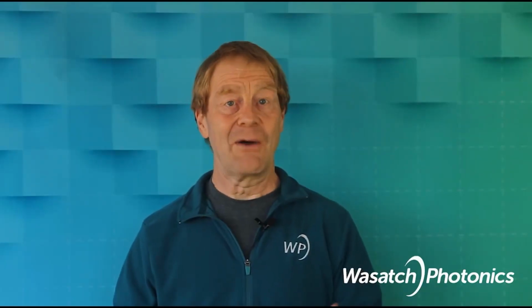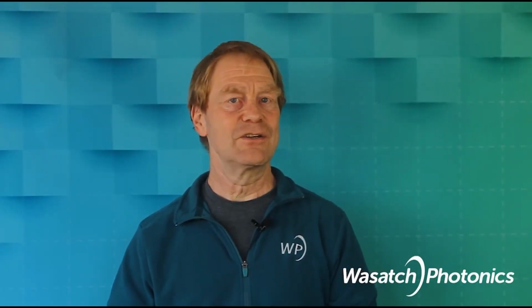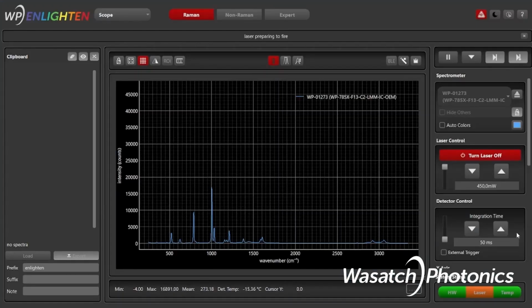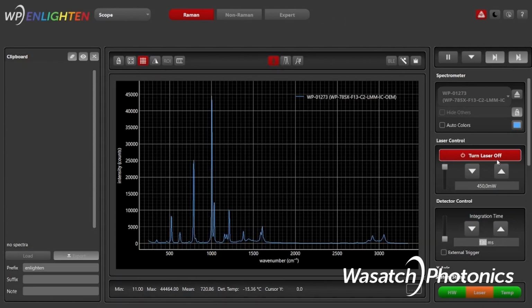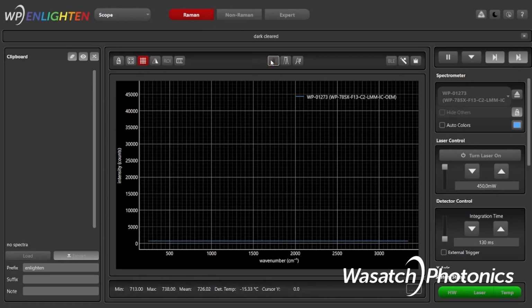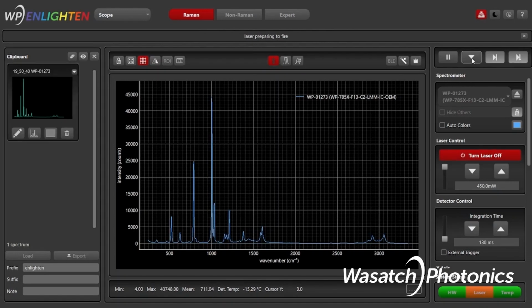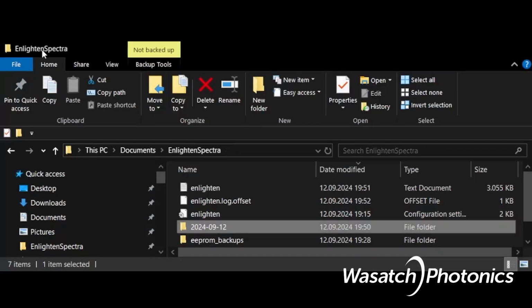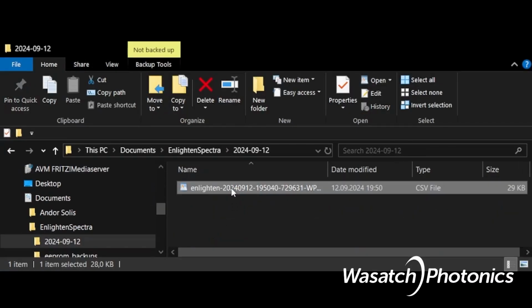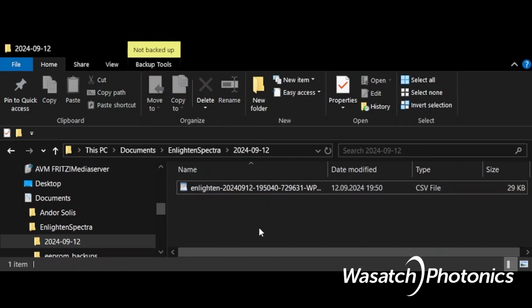But before we can record our actual spectrum, we need to do a few final adjustments in the software. First, adjust the integration time so that the signal reaches maybe around 40,000 counts, which is the scale on the y-axis. We then turn the laser off and save the dark signal, to be subtracted later for a proper baseline. We then turn the laser back on and there it is, your first Raman spectrum. To save your spectrum, click on the down triangle looking capture button. You can find the saved spectrum in the Enlighten Spectra folder in your Documents folder.